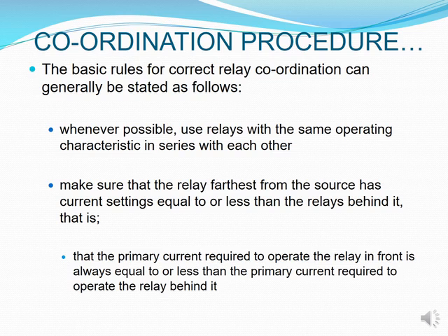Remember, we're working on an impedance scenario. So in other words, at bus E, which is my last bus closest to the load, my current really cannot be more than the one at bus D. It can either be the same because the impedance is the same, or it can be less, okay? Because our impedance at E, we expect it to be more. Why? Because it's got the longest distance on your system. So that is what this scenario is saying.